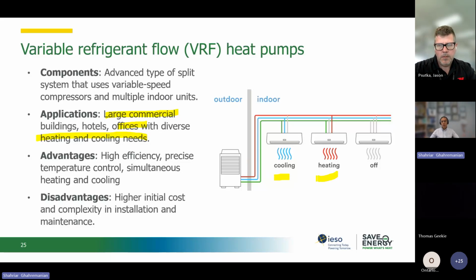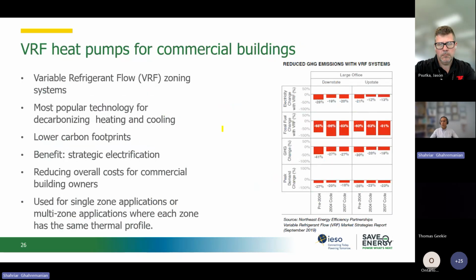So, for example, in a hotel tower, one guest requires heating and another guest requires cooling. Then they can both be served by connecting to these variable refrigerant flow systems actually. They are highly efficient, they have very precise temperature control, and they can provide simultaneous heating and cooling, but they have the highest initial cost and also complexity in installation, and the maintenance needs to be considered for the VRF system. But with VRF systems, we can have different zoning easily done actually, and it's really good for decarbonizing the heating and cooling system. So basically, everything is going to be electrified, similar to other heat pumps, but this is for the entire building.